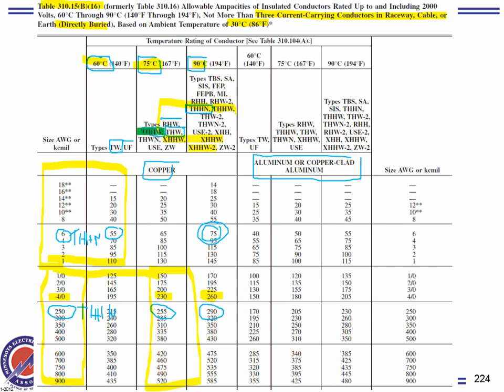Here's an example for you. I have this number 2 conductor, THHN, feeding a design B motor for normal operating condition. Where do I go for that? Because it's feeding a motor. 75, 115. How about if I want to derate? There's bundling. Where do you start when you derate? You start with 130 though.